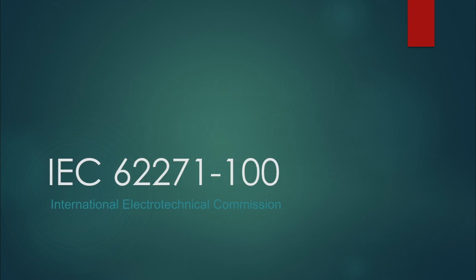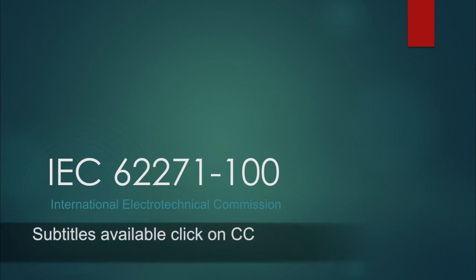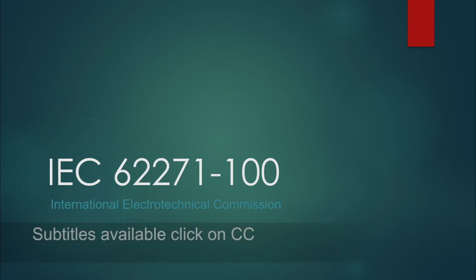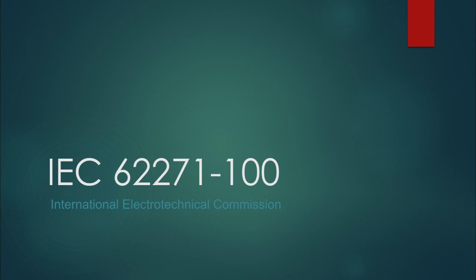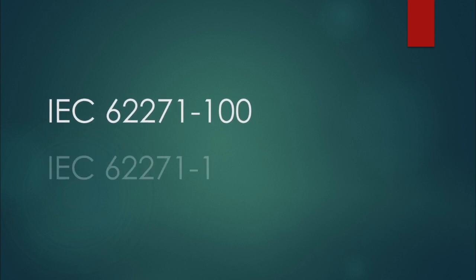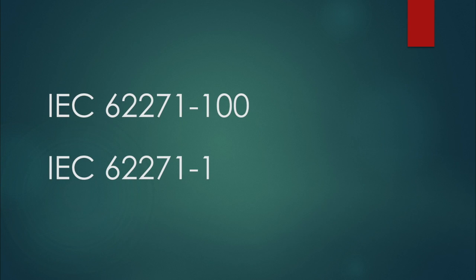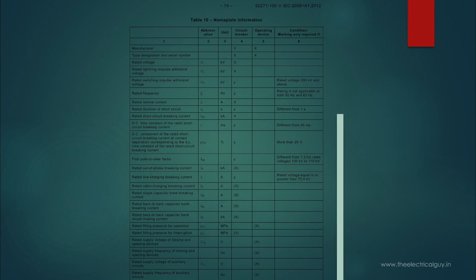In most countries, high voltage switchgears including circuit breakers are manufactured based on the IEC standard, i.e. IEC 62271-100. All the parameters marked on the nameplate of a high voltage circuit breaker are also as per this IEC and also as per IEC 62271-1. So let's first have a look at IEC.